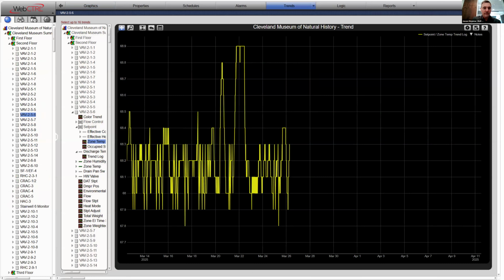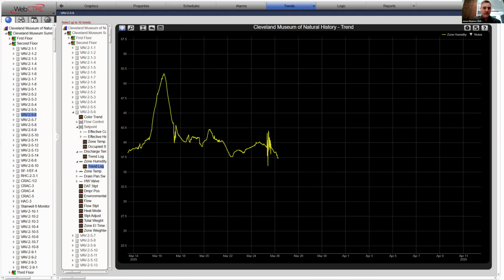Real quick, I wanted to show you some trend data. This is collection storage, keeping at 68 degrees plus or minus 5%. This is the month of March. Using this trend data allows the maintenance team to really make sure things are operating the way they should. This shows humidity trending at 40% plus or minus 5%, but there was a little spike up to 51% before correcting back down.